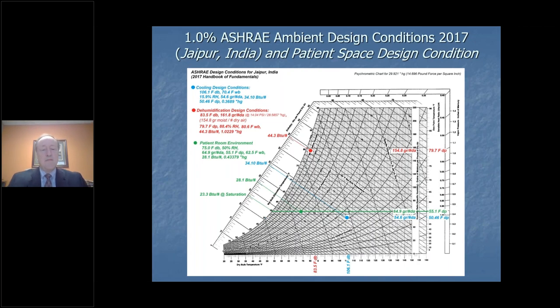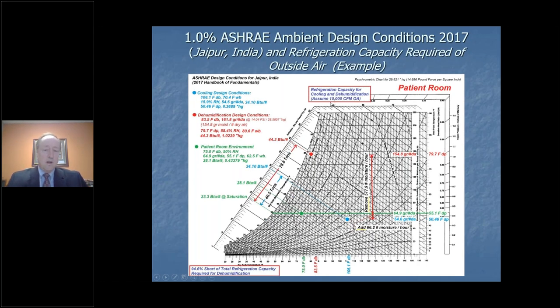Let's say, for example, if I were to precondition the outside air, and in this example, I'm going to require 10,000 cubic feet per minute of outside air to come into my building for ventilation. So I want to know how much dehumidification capacity or refrigeration capacity I need to get from this point to that point, just for the dehumidification and cooling of the outside air. You'll see I need 78.8 tons of cooling. Now, if I wanted to go from this point to that point, I would only need 40.5 tons of refrigeration capacity to go from that point to that point.